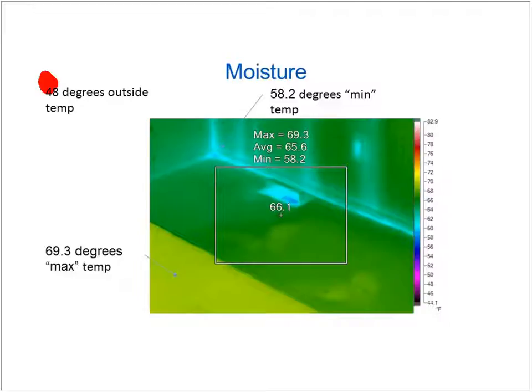By March, when I was called in to look at why the fans weren't working, these units literally had jail bars on the walls where the mold and mildew had attached itself. The fans were failing because they'd shut everything off, and the moisture would go to the fan can, where it was touching the ceiling, outside of the insulated space I should say, and condense on that and fill the back of the fan with water. So literally that setback was allowing condensation to continue to build up on that property over and over, and they finally wound up with the health department red tagging it, and 40 people had to be displaced because it was no longer livable, all because they didn't manage the moisture content in the unit.